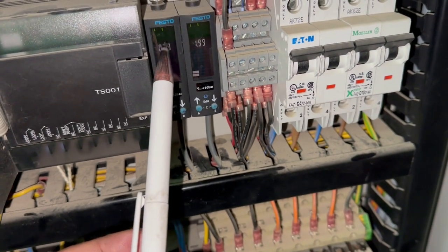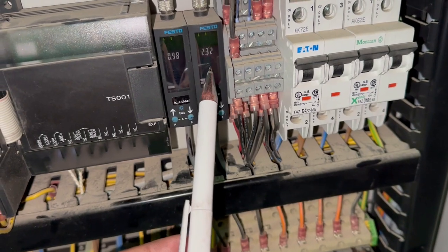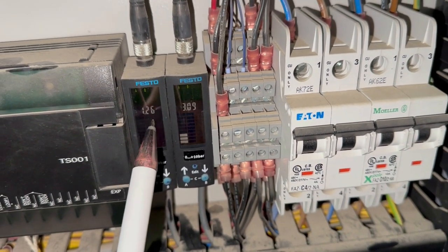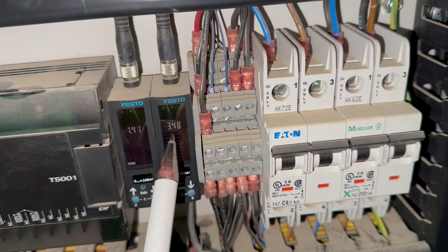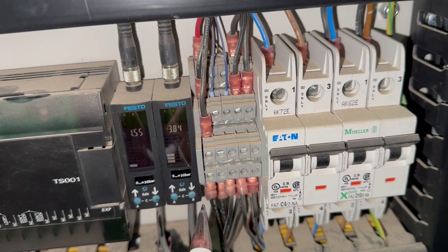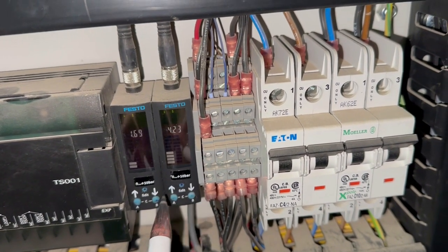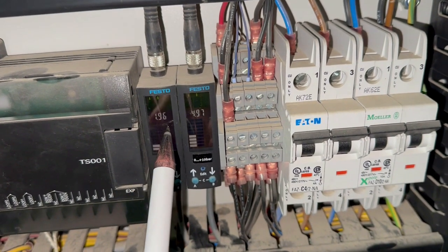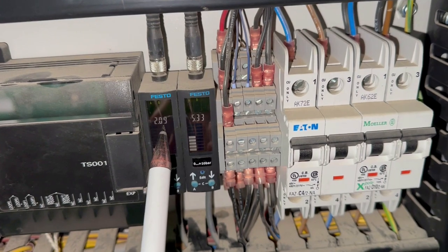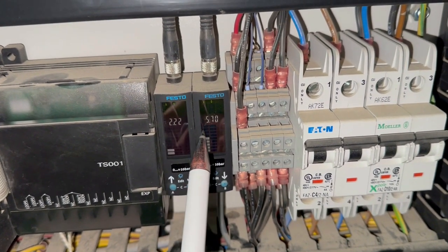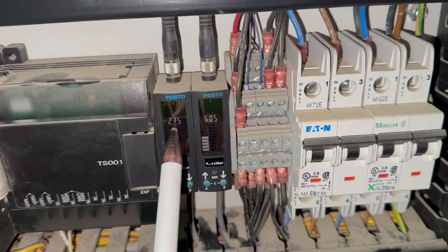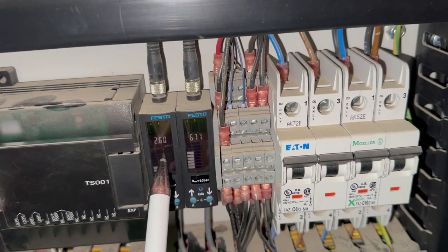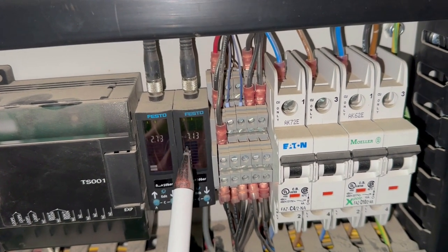So here you can see both pressures are rising, the pressure for the nitrogen and the pressure for the air. One thing important for understanding is, since in the path of nitrogen we have a membrane, and we have only one source, from the air we are extracting the nitrogen. So here you can see this is the air and this is nitrogen. It seems that it's working fine, because the pressure building rate in this chamber is less. So it should be, because this is filtered nitrogen, which is our final product, and this is air. So it means that yes, we are creating the pressure inside the nitrogen tank with nitrogen, and this is the pressure for air.